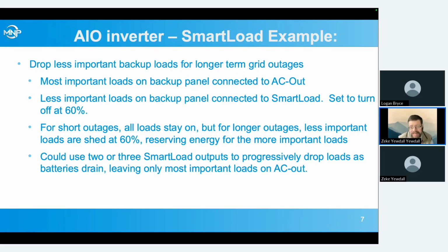We could actually stage multiple backed up load panels with different set points and say, these loads we're only going to run if it's above 90%, which means we're in a real short outage or we've got good sun. Then have another one drop off at 70% and maybe another one at 40%, leaving the last bit just for the most important things. You could also do this same kind of operation scheme in an off-grid setup where you have different loads staged according to importance and keep just your most important ones on your AC out and put your other ones progressively on different smart load outputs.